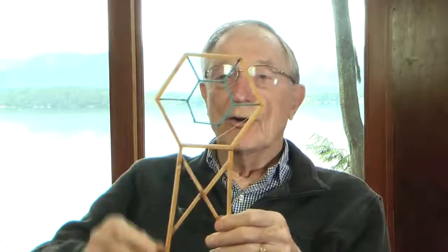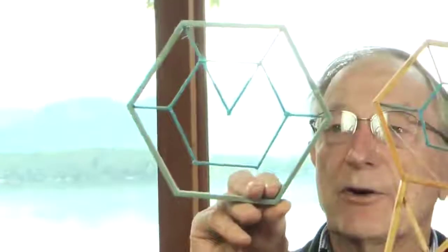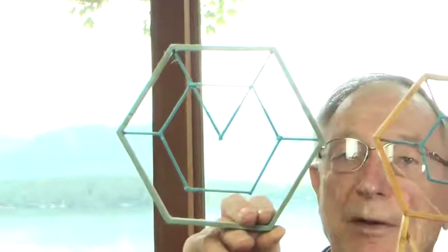We actually built, PTI had a test site in Malta, and we actually built, I made a model of it at the time, I still have it, of how a 6-phase tower might look with these blue lines are the insulators. Here's another one with a center conductor. We built such a line, I tested it. It worked exactly as you would predict it, so the math proved itself. Nobody was surprised.